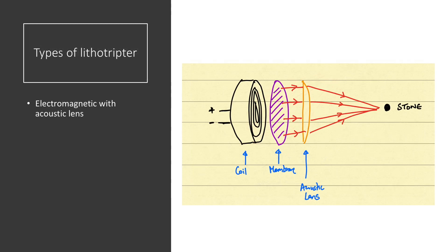The second type of shockwave generator is an electromagnetic device. It relies on the physical principle that when current flows into a metal coil, it induces a magnetic field. If a metallic membrane is placed in close proximity to the coil and the coil is excited by a short electrical pulse, the plate experiences a repulsive magnetic force, generating an acoustic shockwave. If the membrane is flat, the resulting acoustic wave is a planar wave, which can be focused by means of an acoustic lens, as you can see in the first diagram.